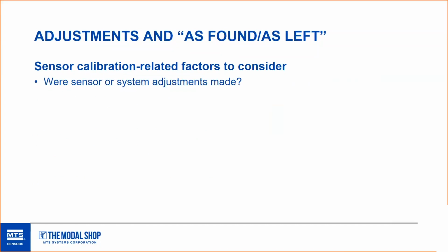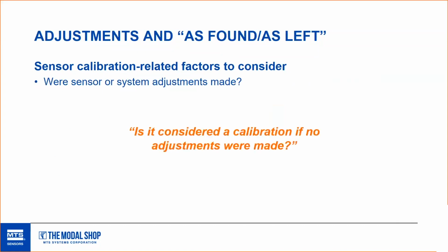And then this is maybe a goofy question, but it's important to think about, were any system or sensor adjustments made? And is it considered a calibration if no adjustments were made? We get that question from time to time, and the answer is yes. For our example that we're picking on a lot today, the poor accelerometer, it's a hermetically sealed unit. It offers no real chance to dig into it and make changes. A calibration is considered a calibration even though nothing was done to it before or after. The data is the same.